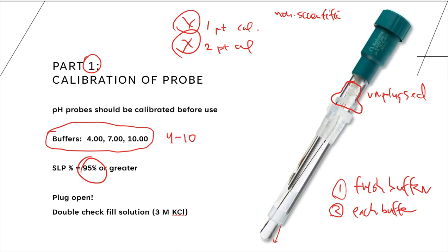But then at the same time, when you get done with the pH probe for the day and your experiment is over, make sure that you plug that hole back. Because this will constantly drain the filling solution. And that filling solution will have to be replenished if you're not very careful and you forget about it and you just let it dangle. With that hole open, it will continuously drip, drip, drip, and you're going to ruin the probe if you're not very careful.